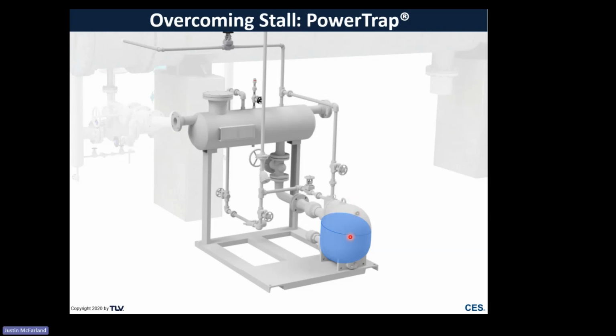There's a device inside this power trap that is basically a high level limit that mechanically senses when it gets to that certain limit, and it's going to engage two sets of valves. It's going to open up a valve here, allowing high pressure motive source, in this case steam, to come in. This would be steam sourced upstream of our modulating control valve. And it's going to close this equalizing line here. So in doing that, it's going to pressurize that pump body and begin pushing out that condensate. Now, all the while, we have condensate that's still coming from the process heater. So we have a check valve here, so our steam's not back feeding into our reservoir and back to our process heater. But because that check valve is closed, then we have a liquid volume that's going to build up.